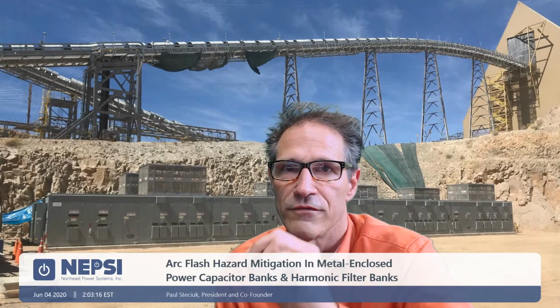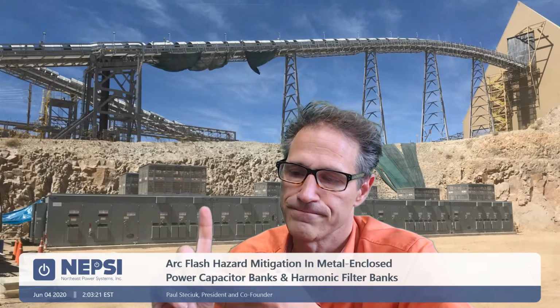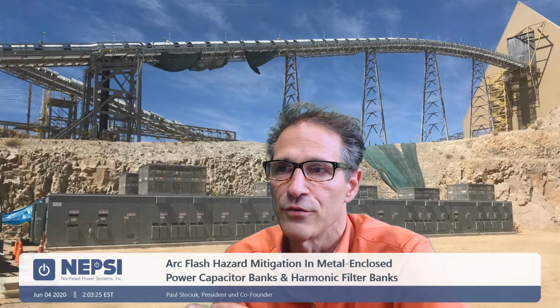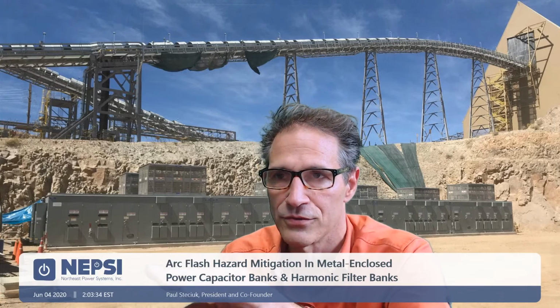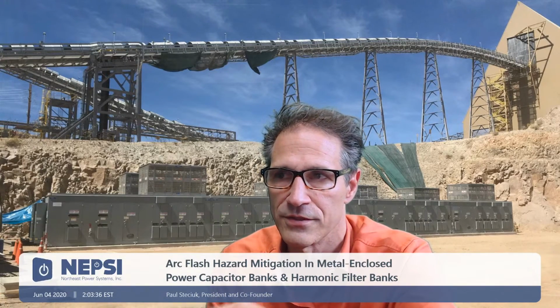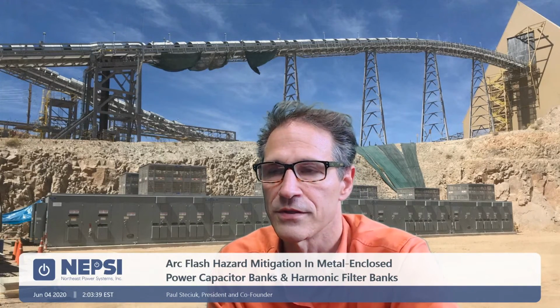The other thing is the actual equipment. When you're supplying equipment into a very critical process facility, LNG plants, mine applications, petrochemical plants, those types of facilities, arc flash hazard mitigation also speaks to the reliability of the equipment. If we have an arc flash event inside this enclosure, it will be an explosion. The explosion will put the equipment out of service. So you always have to think about, well, what is the cost for downtime? And sometimes downtime for equipment like this could be millions of dollars per day.